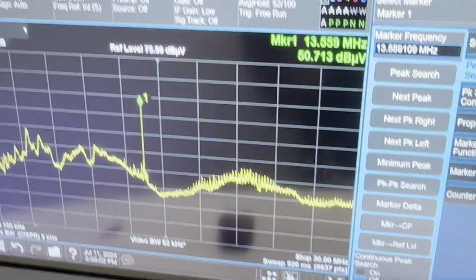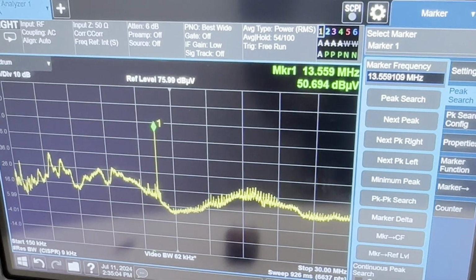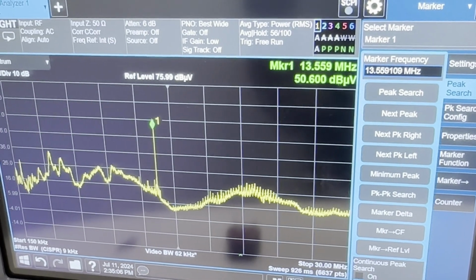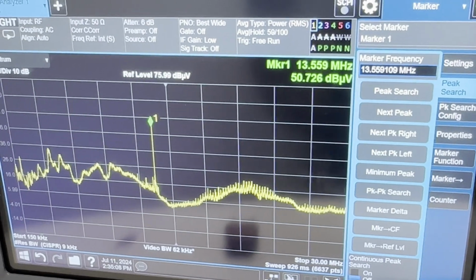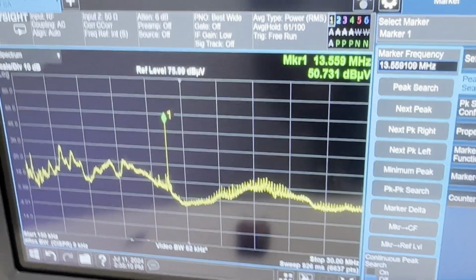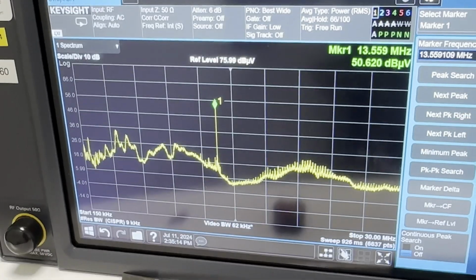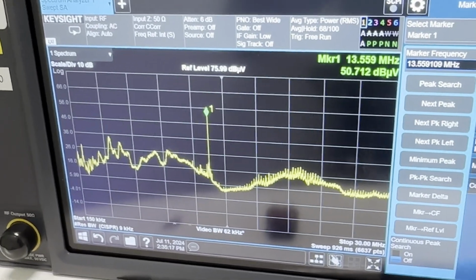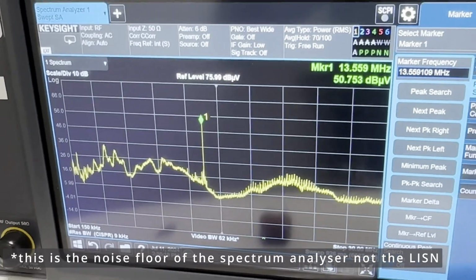megahertz, and this is caused by an NFC reader that is enabled somewhere in the building on this ring main circuit. So this is basically the noise, and that's not going to go away unless I isolate the mains for the LISN, which I don't have the equipment to do.